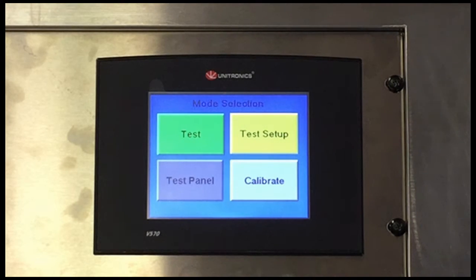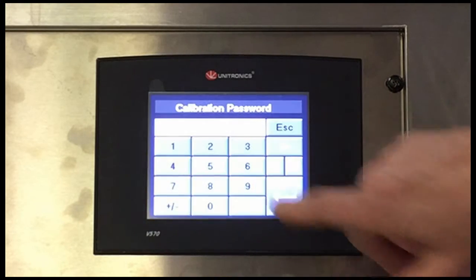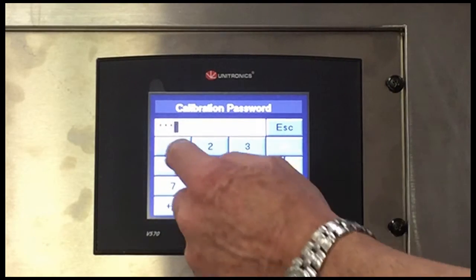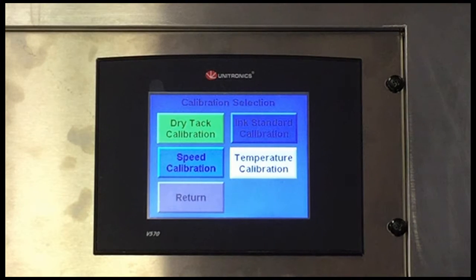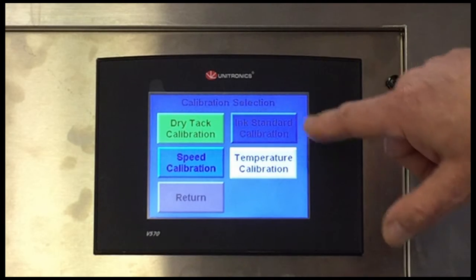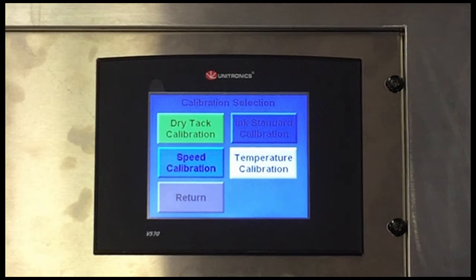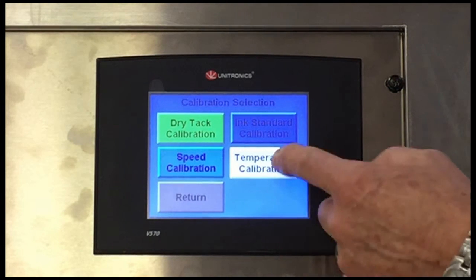All right, the last section of the touchscreen is the calibration, and again, we have this password protected because you don't want the operator necessarily to get in and be able to change your calibration. We have 4 different areas for the calibration. We're going to talk about 3 of them, and then we're actually going to perform the 4th one. The temperature calibration is actually very straightforward. I had mentioned a few minutes ago that we sell an external temperature probe that will measure the water temperature and display it on the screen. All the temperature calibration is going to do is it tells you to set your, in fact, we'll just walk through it.